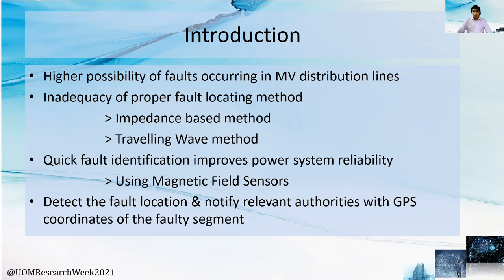In the impedance-based method, the impedance seen by two ends of the faulty line is calculated and the fault location is identified based on the impedance profile of the line. The traveling-wave method basically relies on the time taken by the faulty wave to reach the fault detectors.